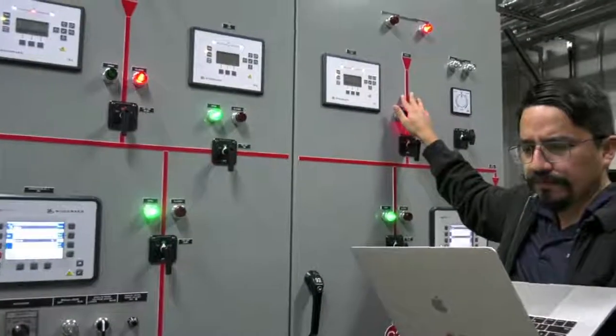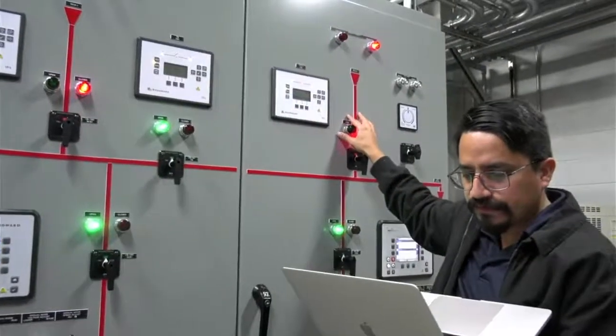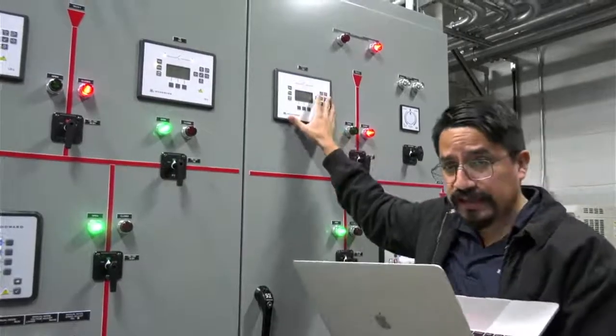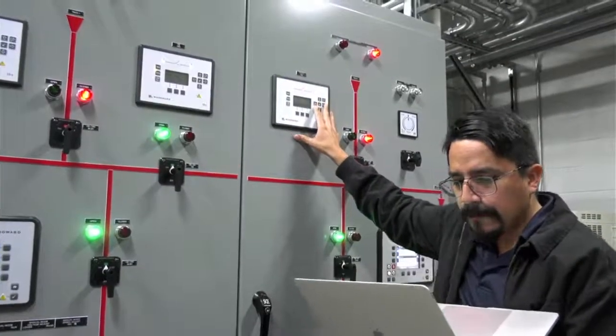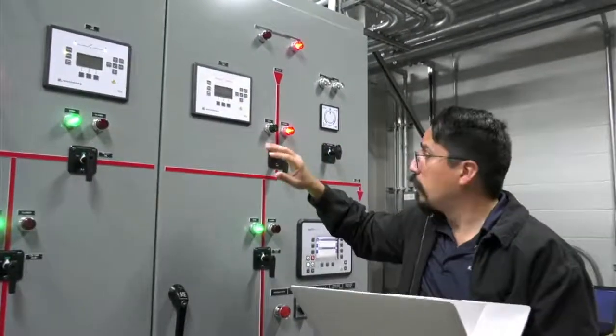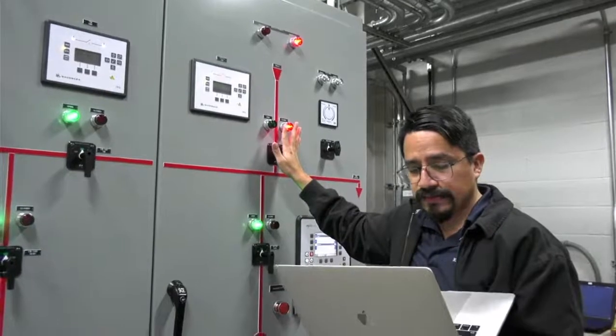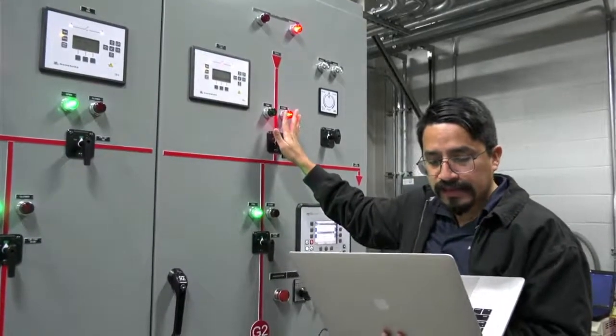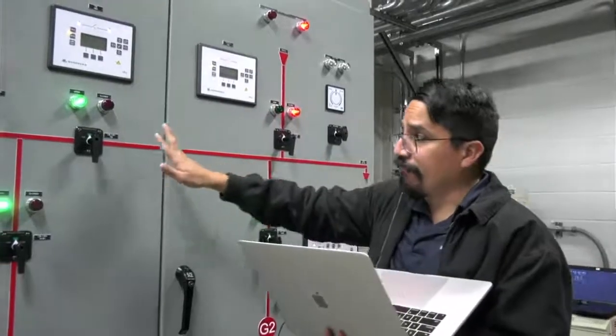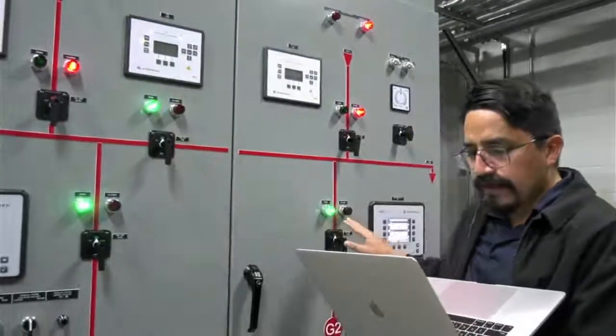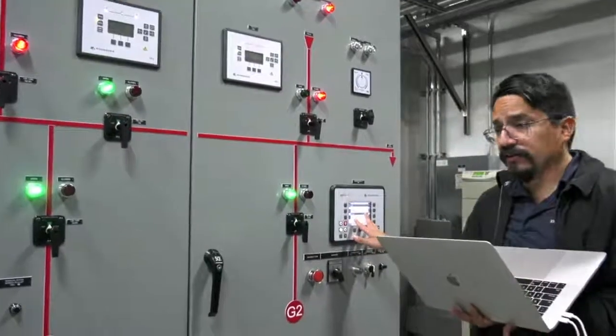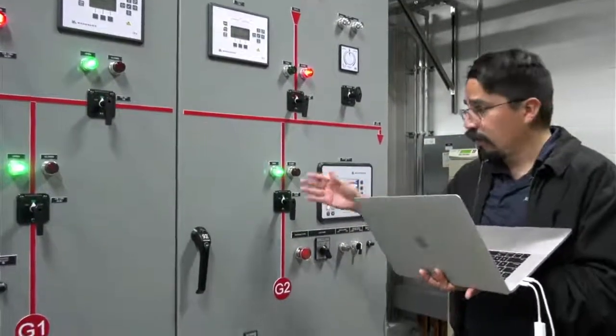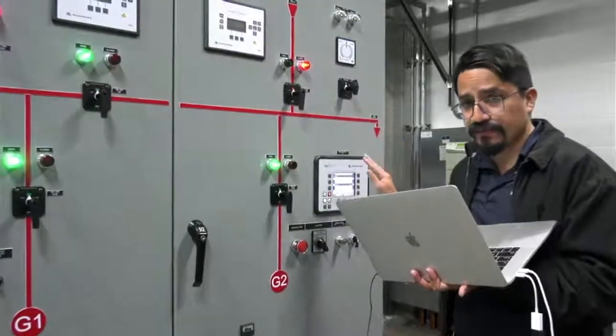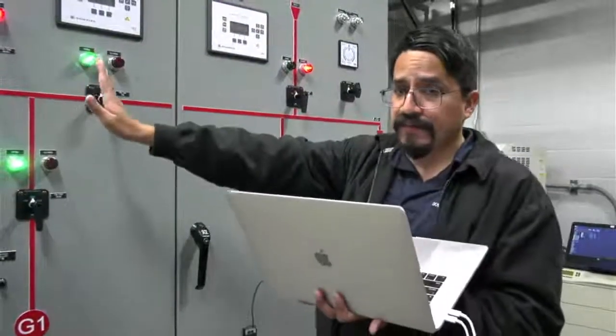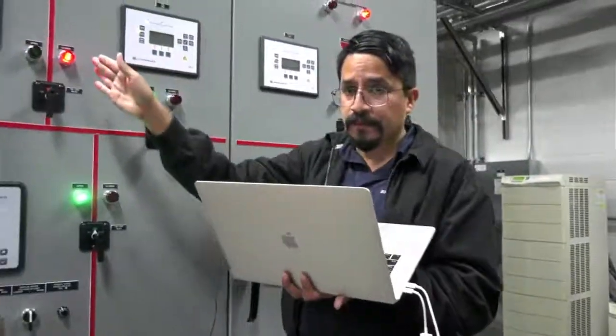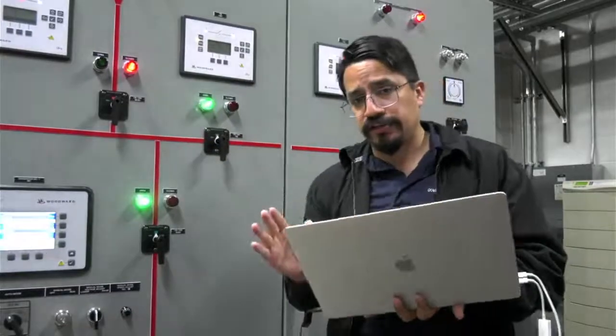Let's say Tico 2. If Tico 2 fails, CB2 is going to detect the failure. After the delay, the same as before, it's going to open the main breaker, right? The tiebreaker will remain open. The generator on this side is going to run and it's going to close and energize this side of the bus. The other side is going to remain on Tico 1. Right? That's the priority on generators.